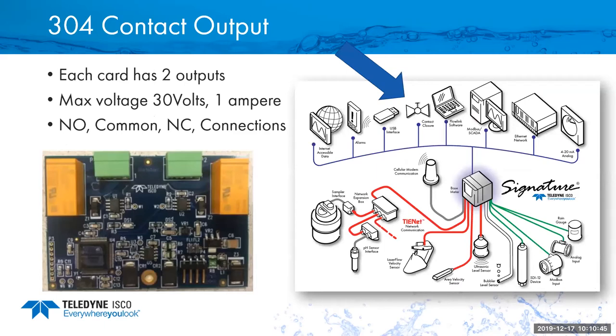The 304 contact closure is a way of either alarming or pulsing based off of doing what's called a momentary closure based off of a flow pulse. You can create that out of the signature flow meter. Now, the maximum voltage for a contact output is 30 volts or 1 amp. It does have normally open, normally closed, and common connections. So you can either alarm off of this or use it as a momentary closure for some condition.